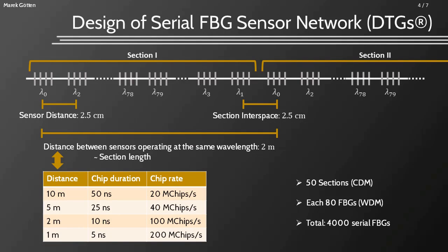Here you can see the design of our 4,000 FBG sensor network. The FBG sensors are so-called draw tower gratings, DTGs. We have several WDM sections with sensors operating at different wavelengths, multiplexed by WDM. There are 80 different wavelengths in one section — first all even wavelengths upwards and then all odd wavelengths downwards. The distance between the sensors is set to 2.5 centimeters. The whole network contains 50 of these identical sections placed right behind each other, so that the distance between the last and the first sensor of the next section is also 2.5 centimeters, achieving an equal distribution of sensors. The distance between sensors operating at the same wavelength is 2 meters, which also equals the section length.